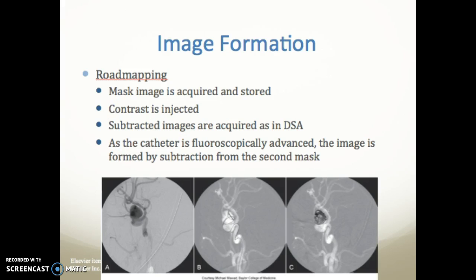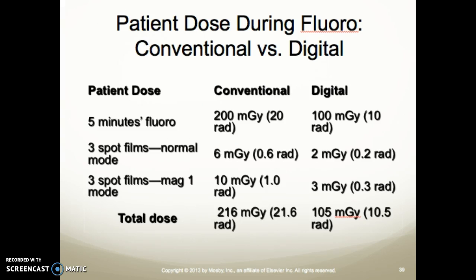Road mapping involves acquiring and storing mask images, injecting contrast, acquiring subtracted images via digital subtraction, and as the catheter is fluoroscopically advanced, forming images by subtraction from a second mask. Regarding dose comparison — conventional versus digital — five minutes of fluoroscopy gives about 20 rad conventional versus about 10 rad digital. Spot films in normal mode: 0.6 rad conventional versus 0.2 rad digital. The total dose using digital is about half, which is a significant reduction.